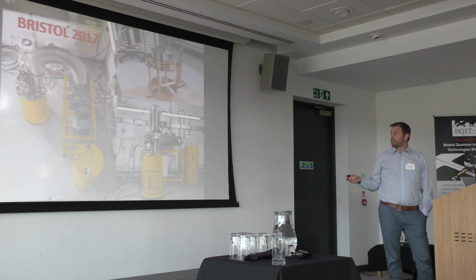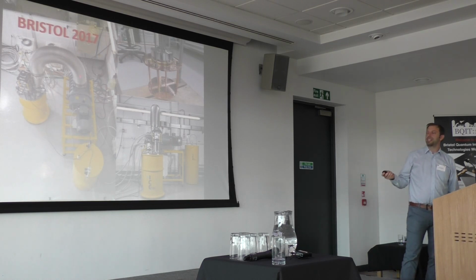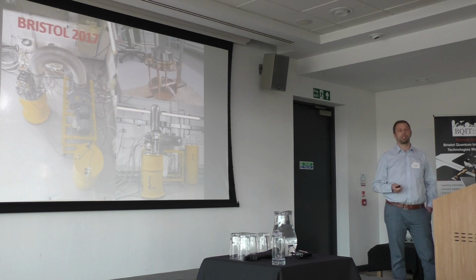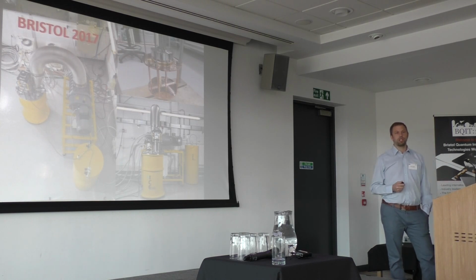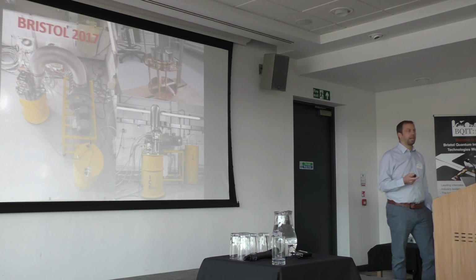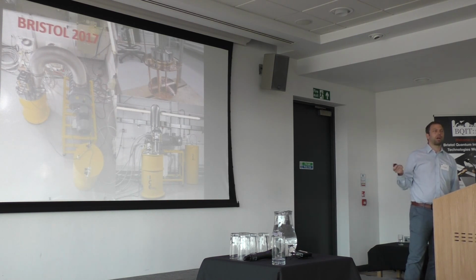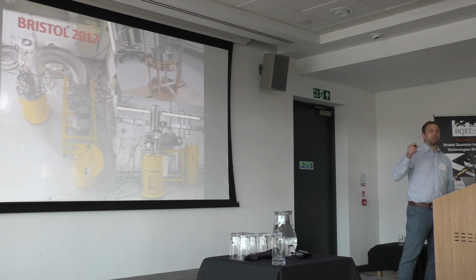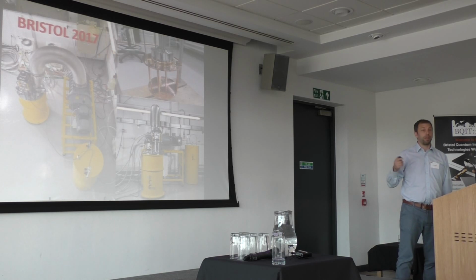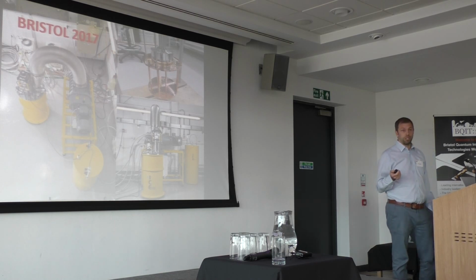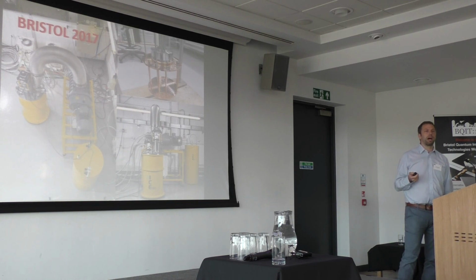And then the pump itself obviously is producing a huge amount of vibration, which is transmitted down this pumping line, but that's a little easier to isolate. You can just put that pumping line in concrete blocks or through a wall or something to really hold it rigidly and remove those vibrations. So that's not too bad. We installed it here and there was a vibration specification of sub 10 microns for Bristol, which is what they thought would be the limit where it starts to affect their experiment. And we're within that at the moment. For dilution fridges, the requirement seems to be heading more towards sub 100 nanometer levels of vibration for their experiments, which again is a lot harder to do when you're using these mechanical cold heads and pumps.